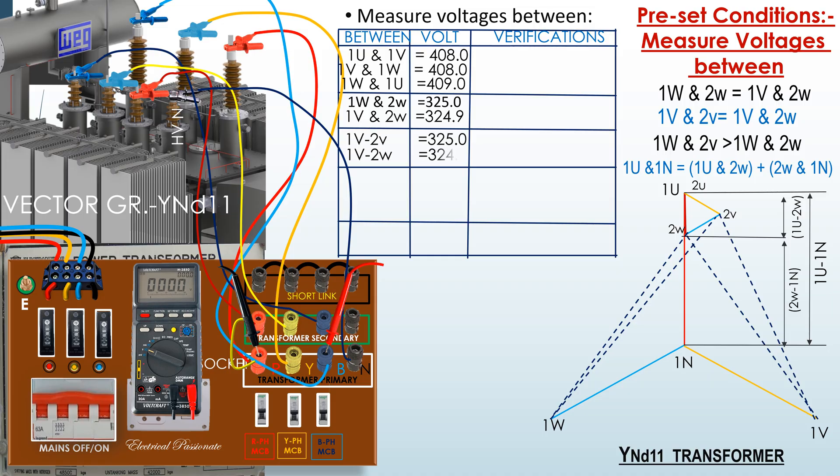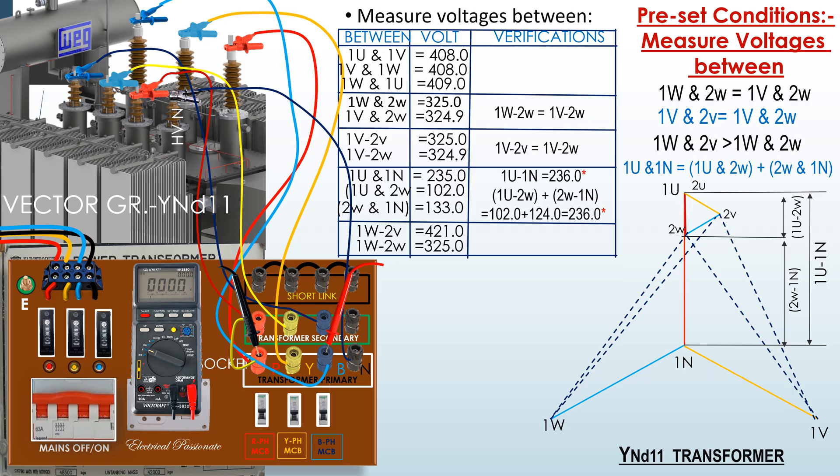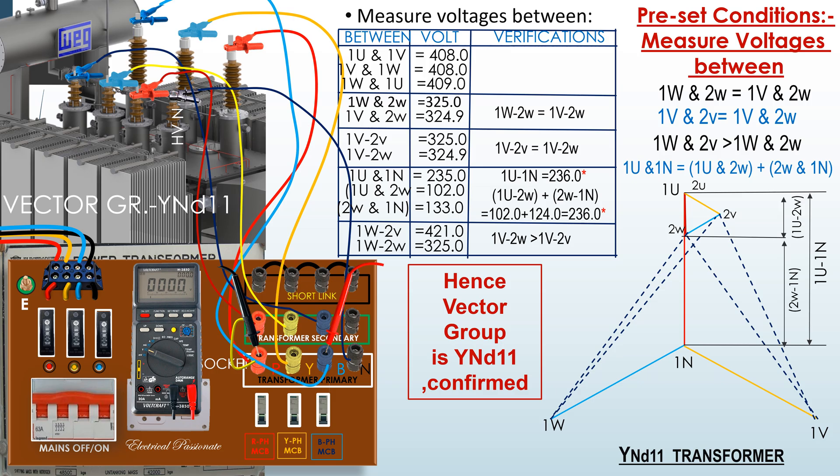We are to verify the measured voltage according to preset conditions. Here we see the results satisfying all conditions of vector group YND11. Hence, vector group is YND11 confirmed.